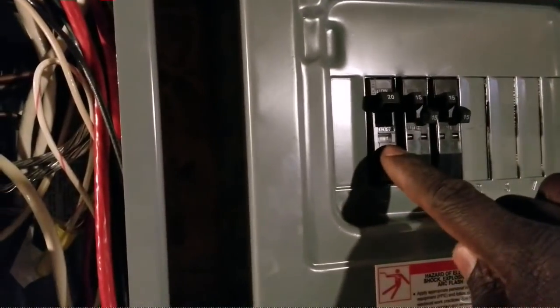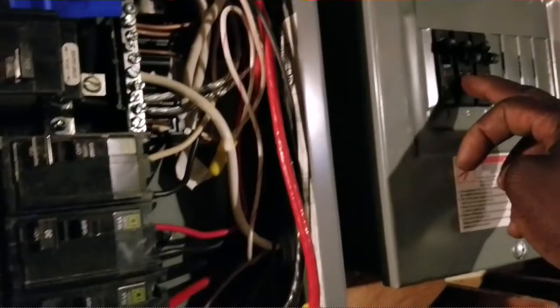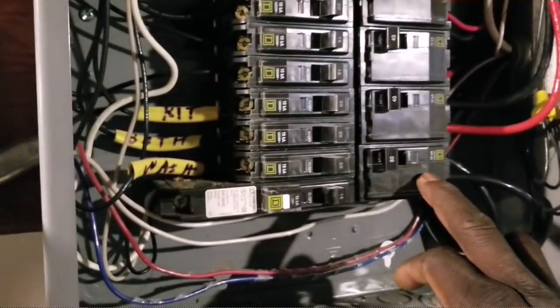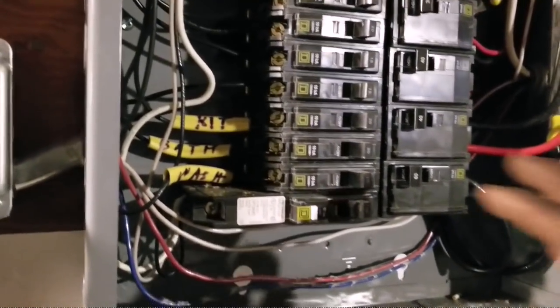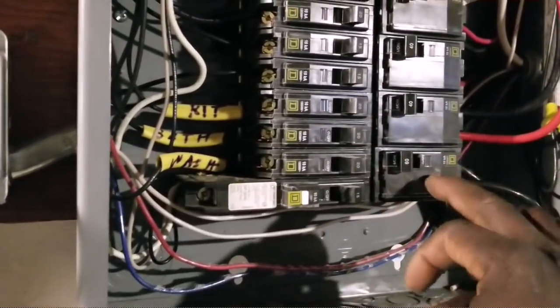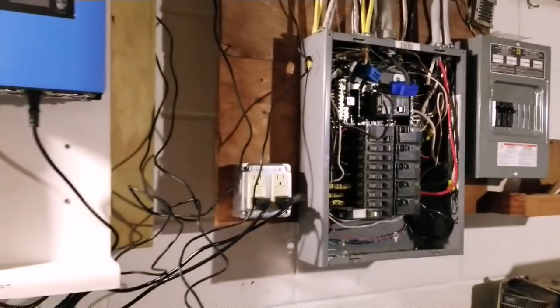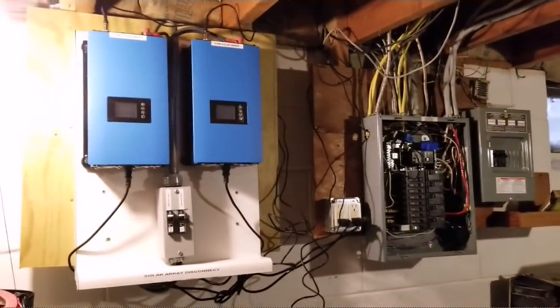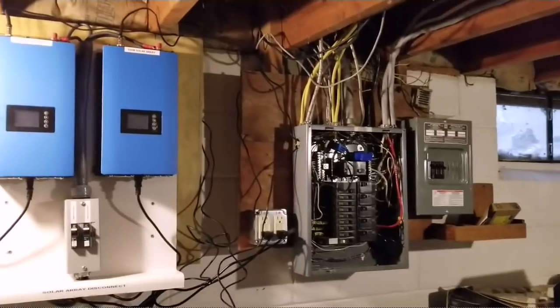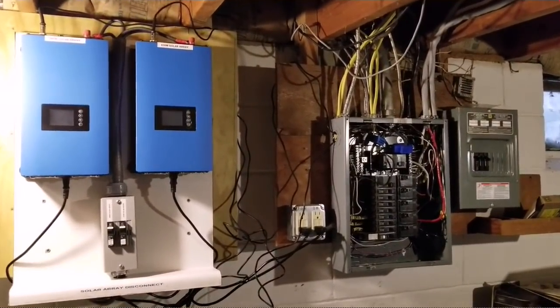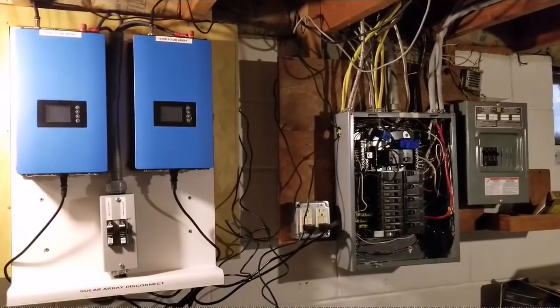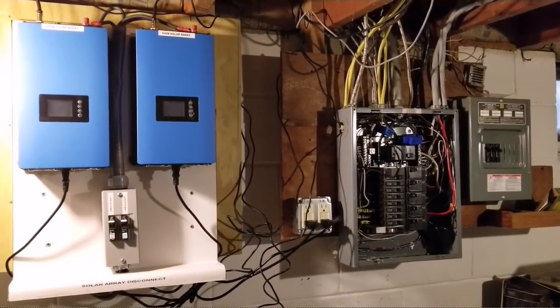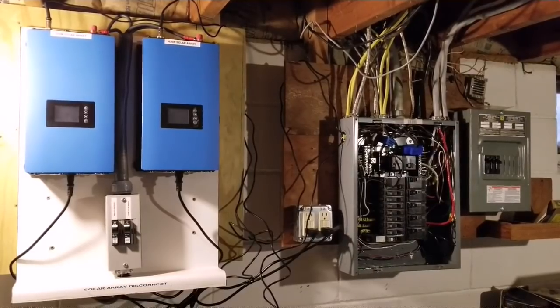It's hooked up to this 60 amp, so it's pulling everything and transmits here. The inverters are pushing power from here and throwing them into this breaker, which is a 60 amp breaker, but it's energizing both legs because it's 240 - it's a 240 breaker. I hope you guys enjoy this install. I'm going to be doing all the wire management now properly and close that box. We're complete, we call it a day. Bye.